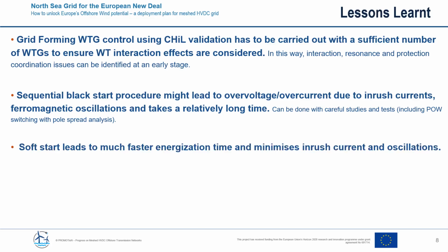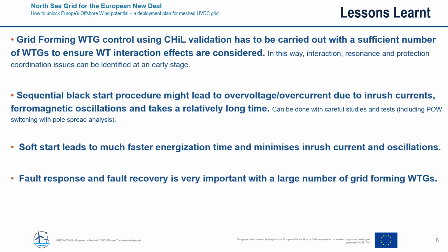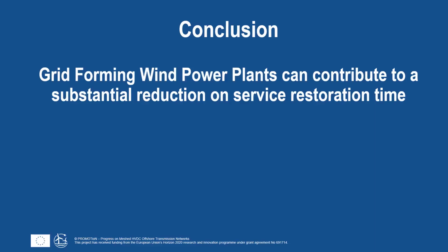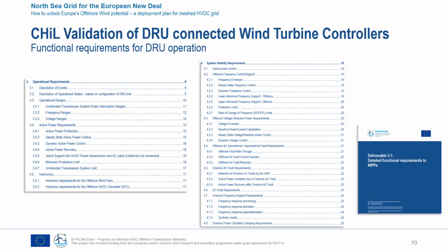On the other hand, soft start leads to much faster energization and very small inrush currents and oscillations. Finally, fault response and fault recovery coordination is extremely important when we have a very large number of grid-forming wind turbines. The main conclusion is that grid-forming wind power plants can contribute to a substantial reduction on service restoration time after a blackout. For the second part of the presentation, I'm going to show the control hardware in the loop validation of DRU-connected wind turbine controllers.